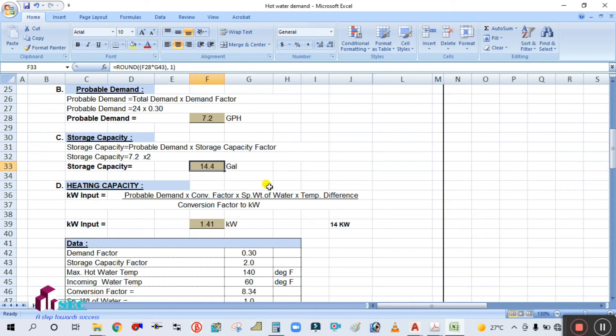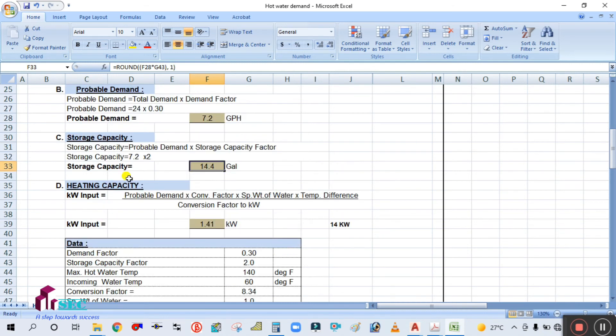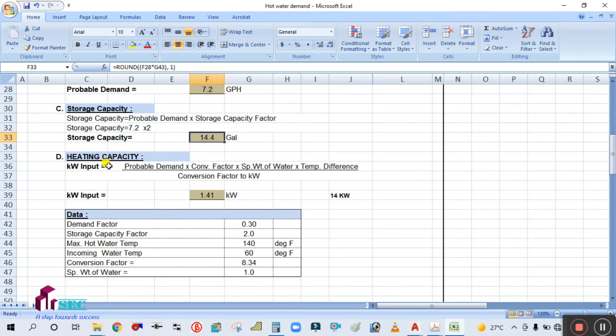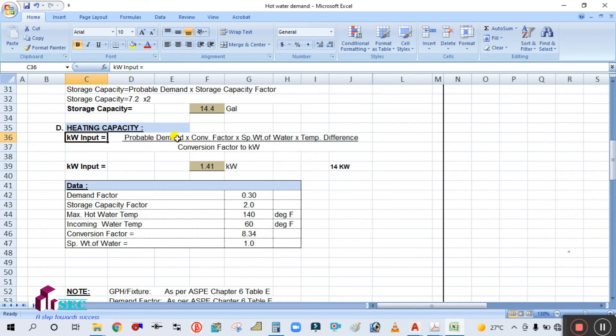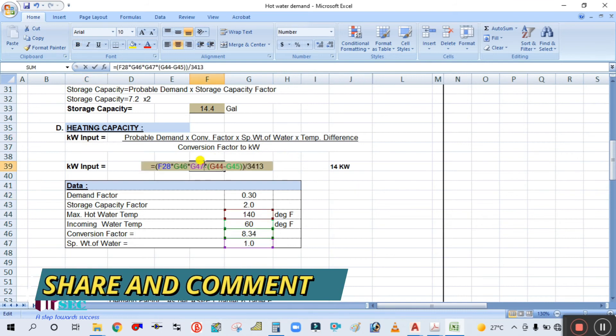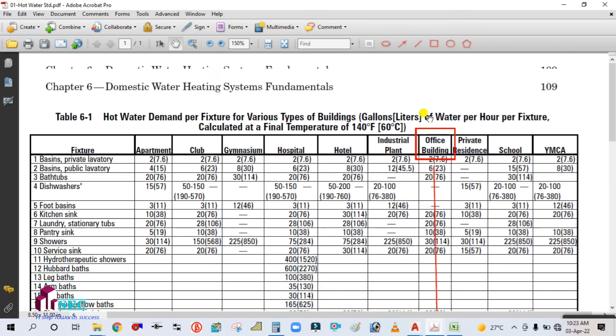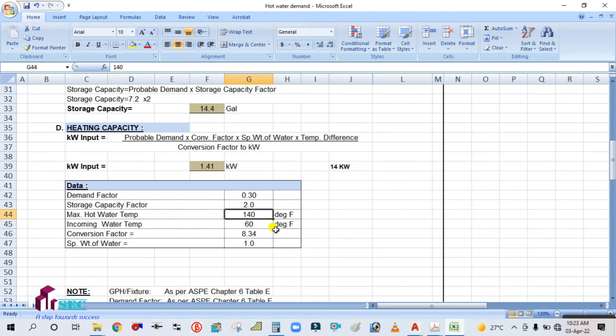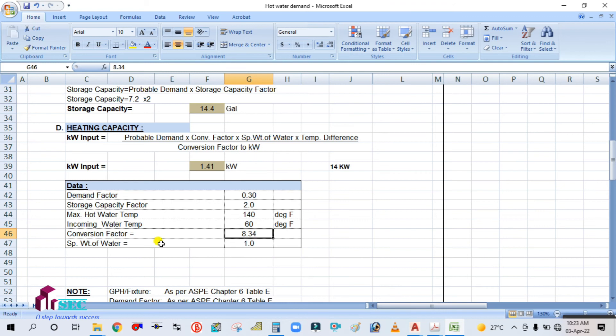The storage capacity is 14.4 gallons. So a 14.4-gallon water heater is required. Now we calculate the heating capacity in kilowatts. The formula is: Probable Demand × Conversion Factor × Specific Gravity of Water × Temperature Difference ÷ Conversion Factor to kilowatt. The maximum hot water temperature is 140°F and normal water is 60°F. The conversion factor for kilowatt calculation is 8.34, and specific gravity of water is 1.